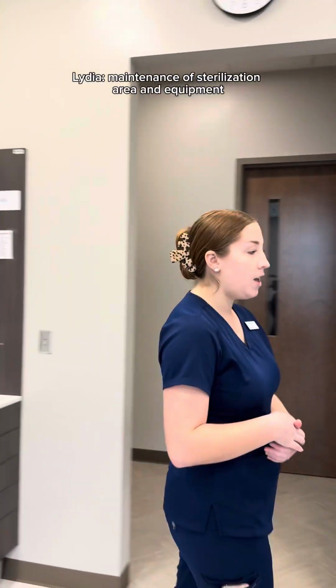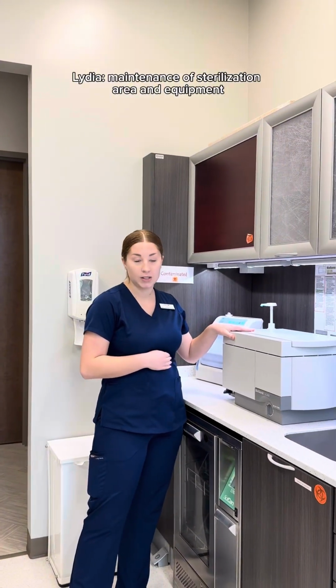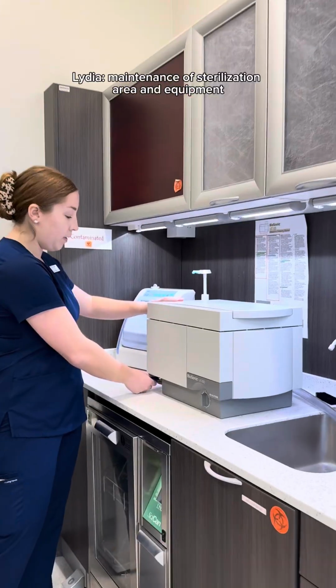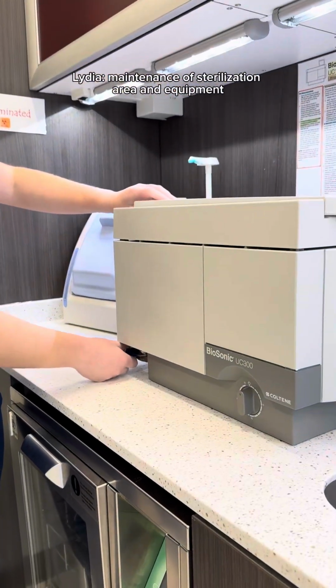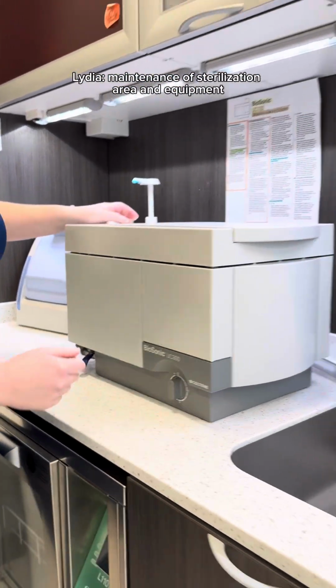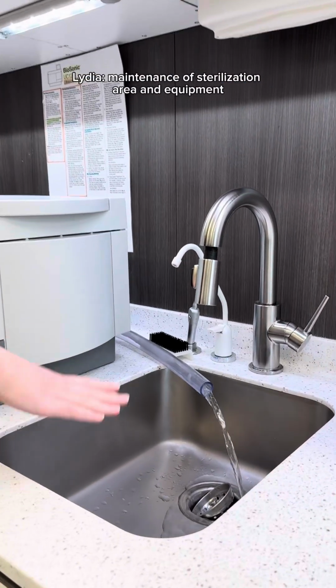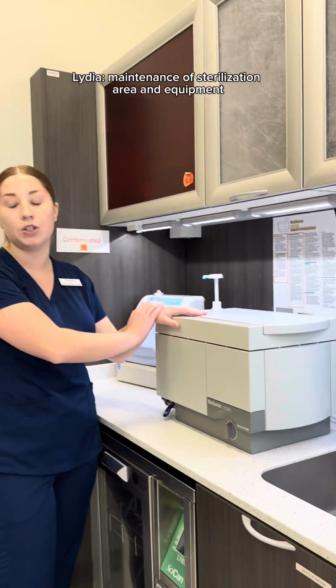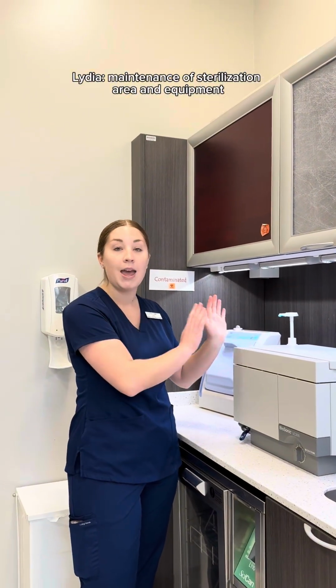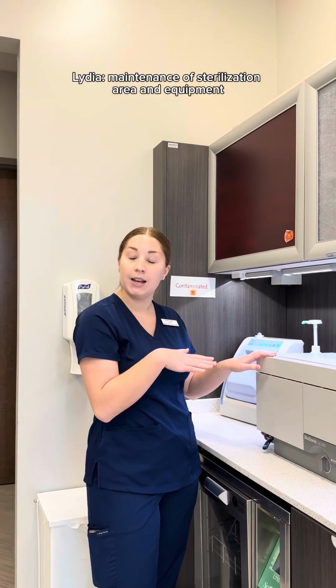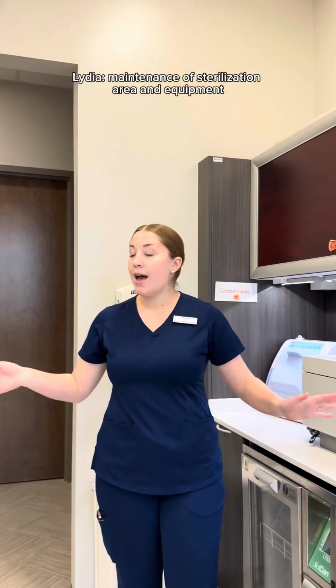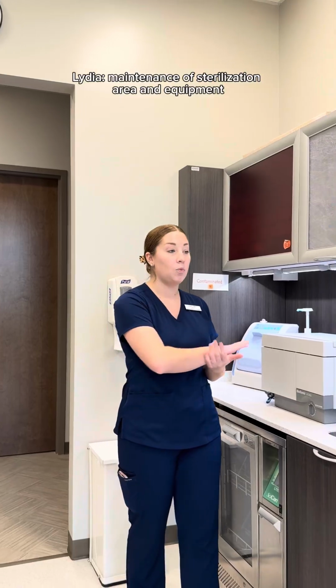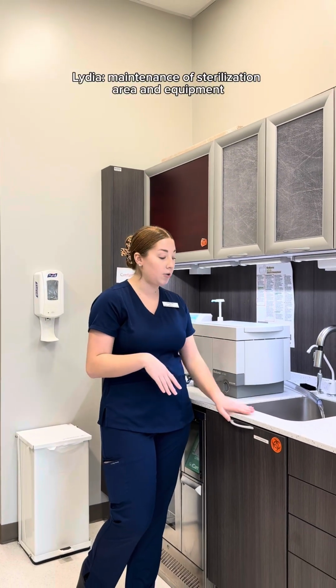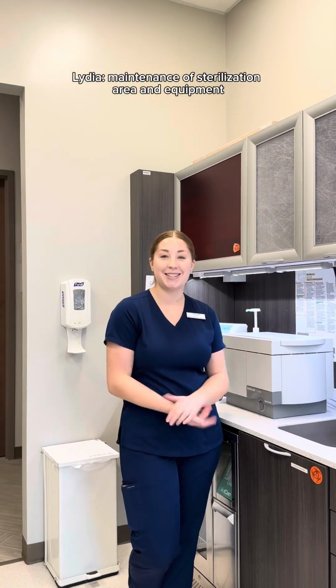Then at the end of the day, you also want to drain the ultrasonic. You can do this by flipping this lever right down here to open, and the water will begin to drain through this tube here. You also want to do this throughout the day if the ultrasonic becomes visibly soiled. After it's drained all the way, you can pre-clean and disinfect. And then overall, at the end of the day, you can use a wipe to pre-clean and disinfect all your counters, contact surfaces, and sinks.